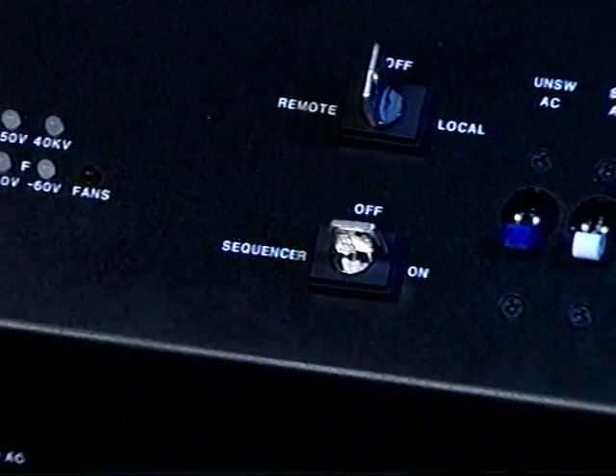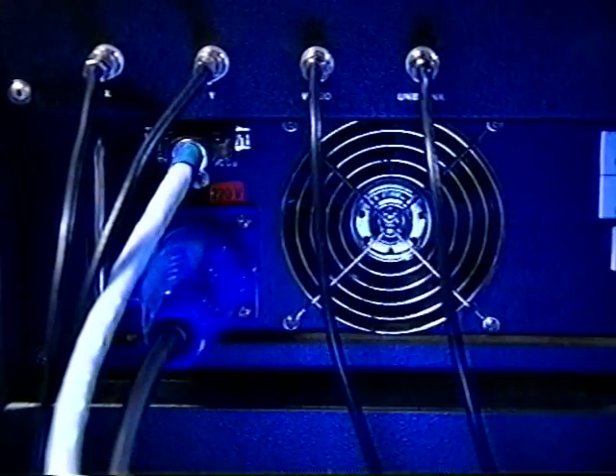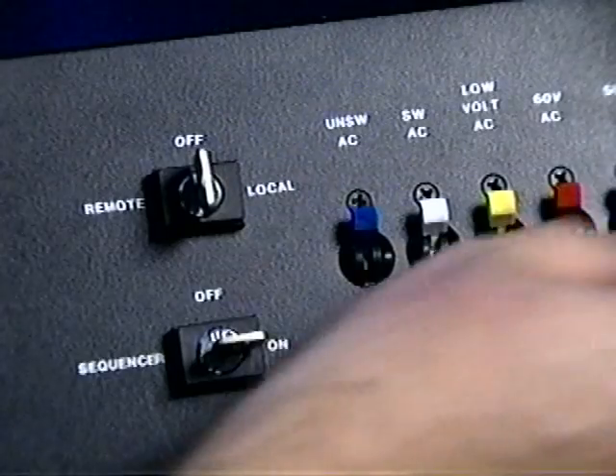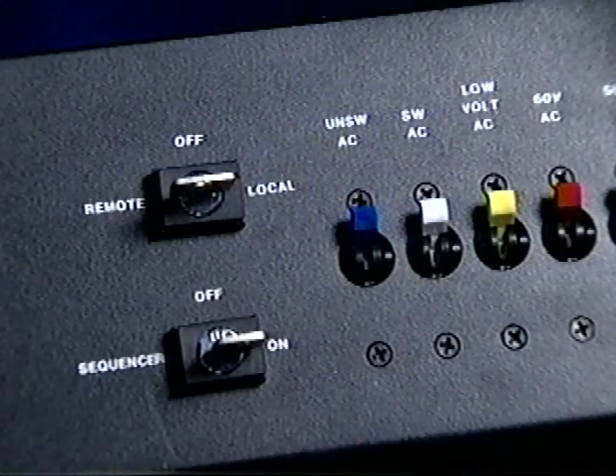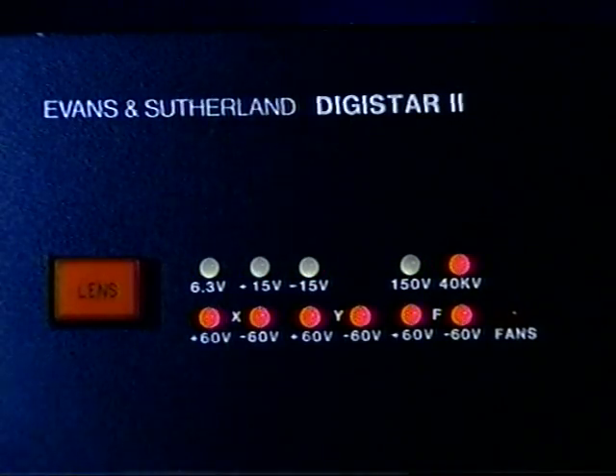This is the normal position for this switch. Reconnect the AC power cord. Place all power drawer circuit breakers in the 1 or on position. Wait 10 seconds, then turn the projector mode key switch to the local position. The projector should power up normally.